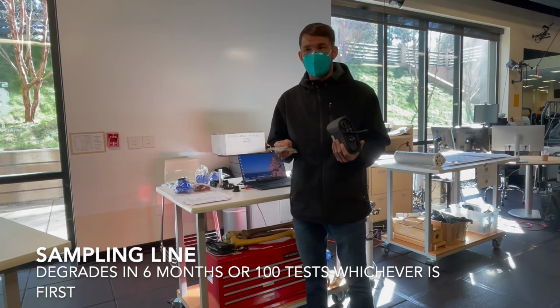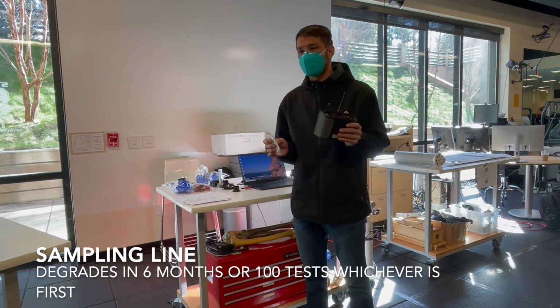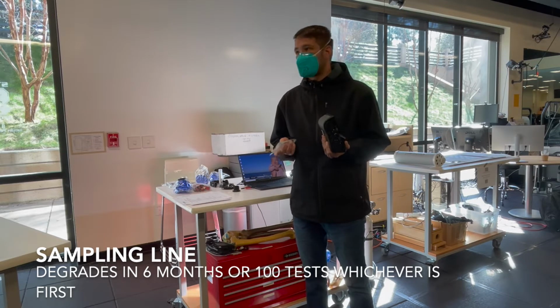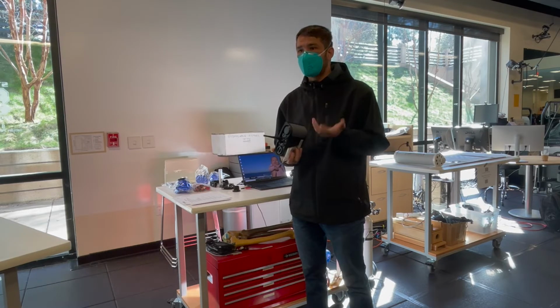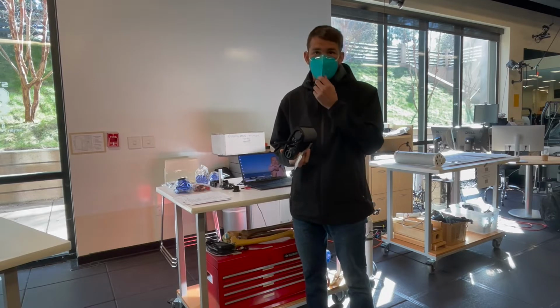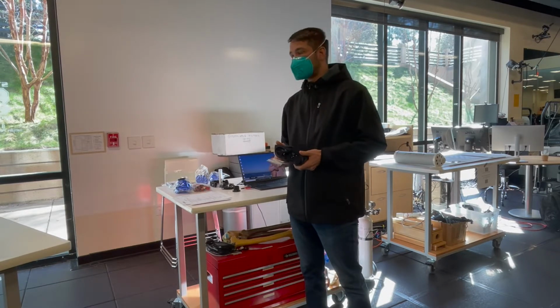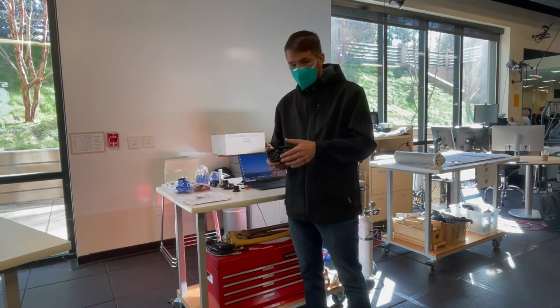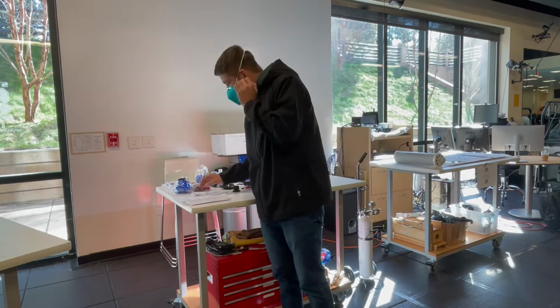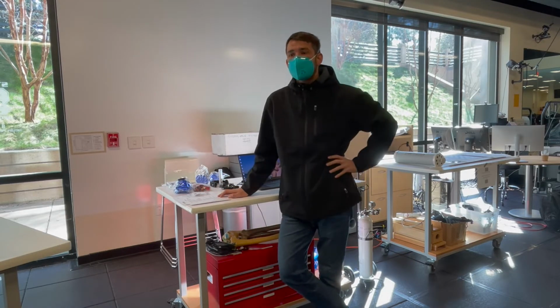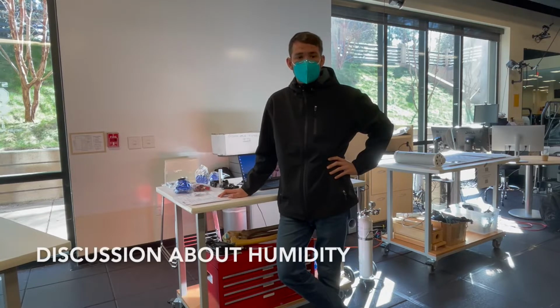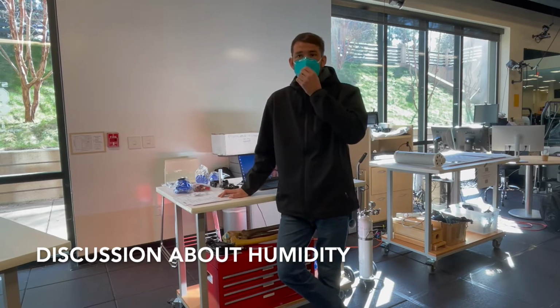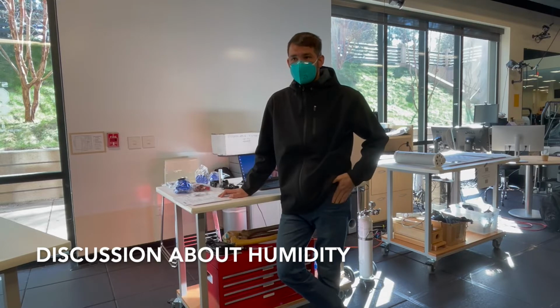Those are both really important things to keep up on, to make sure that your data is good and the system's calibrating appropriately. So be mindful of those dates and make sure that when it needs it, you order that stuff in advance. I'm going to go ahead and pass it. I don't think you guys should ever have an issue with the environmental conditions of use. It can operate within spec up to 15,000 feet or 4,900 meters or so. So no issues there. The humidity specs are between 5 and 90%. When you get to the very low end, you can have electrostatic discharge issues.